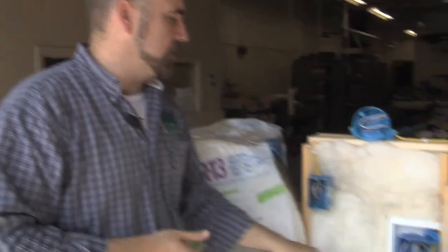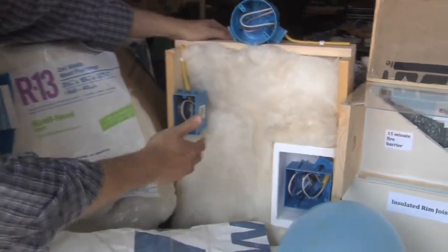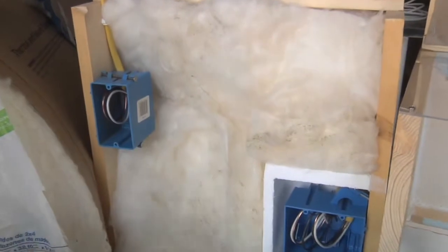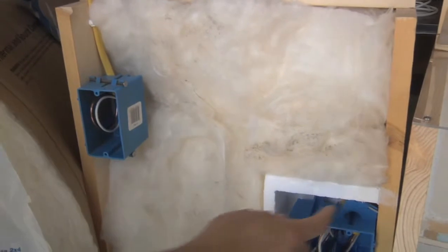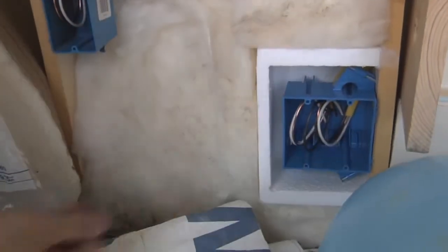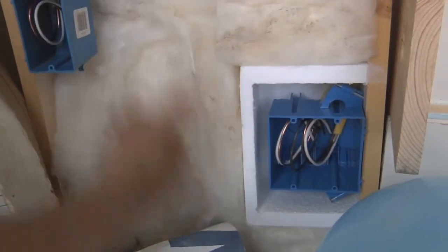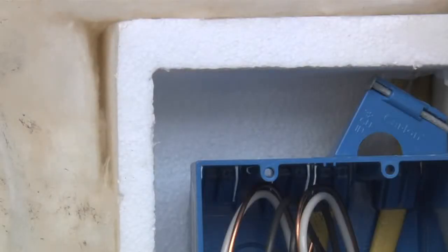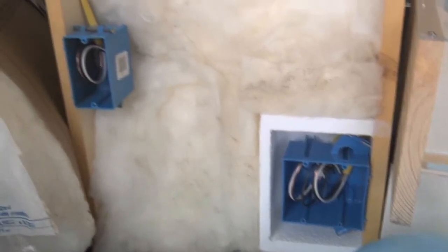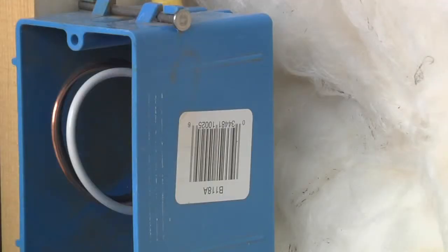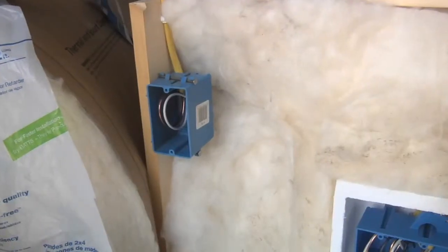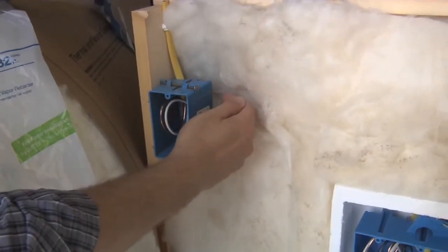If we look at this mock wall cavity that we have here, we can see that obviously there are some different things going on. First of all, we know that heat can transfer right through building materials, but air can also pass through these electrical boxes and into that wall cavity and get air currents moving in there. In this installation over here, they installed this energy block, which keeps that air from moving through there. And on this other side, where it's not installed properly, we've simply taken the fiberglass and smashed it in between, compressing that fiberglass and reducing its R value. It's not going to resist that heat loss as well.